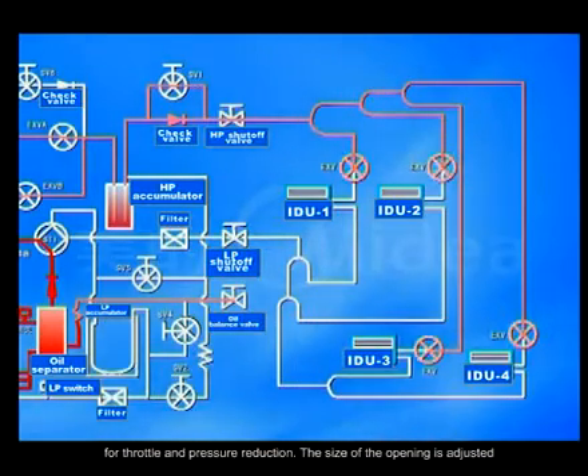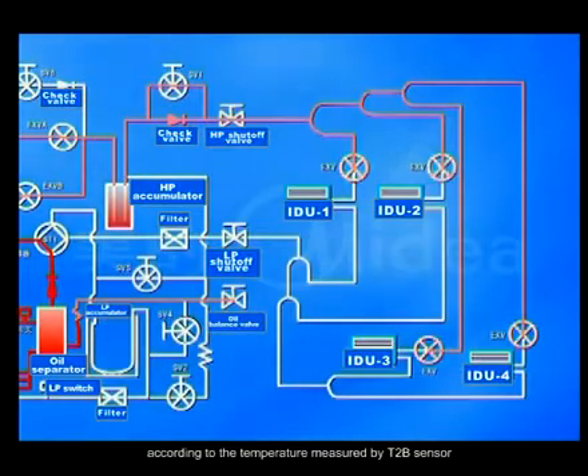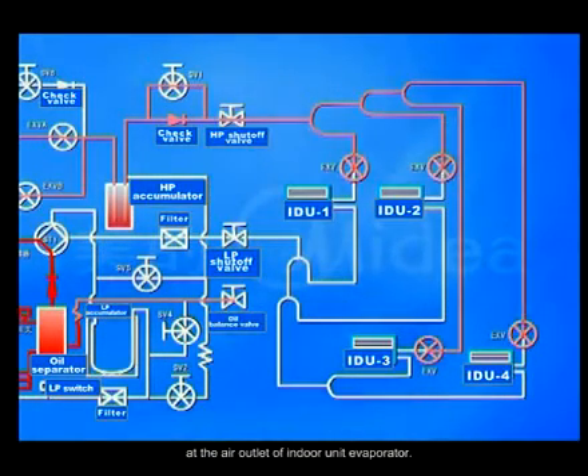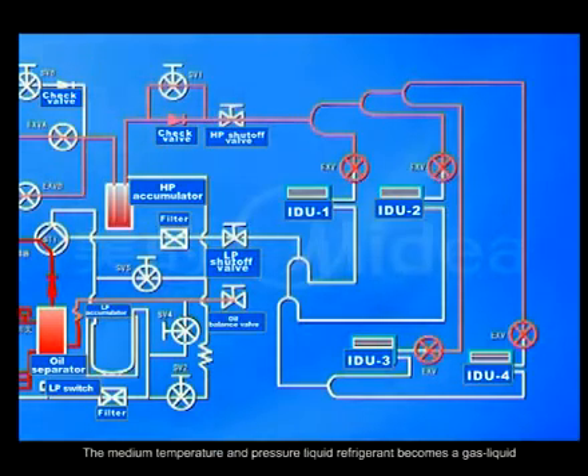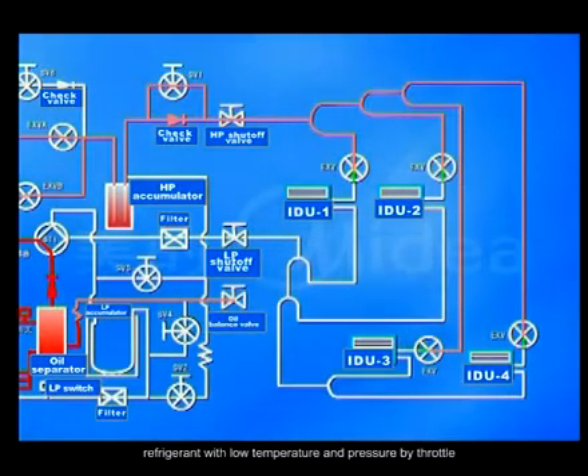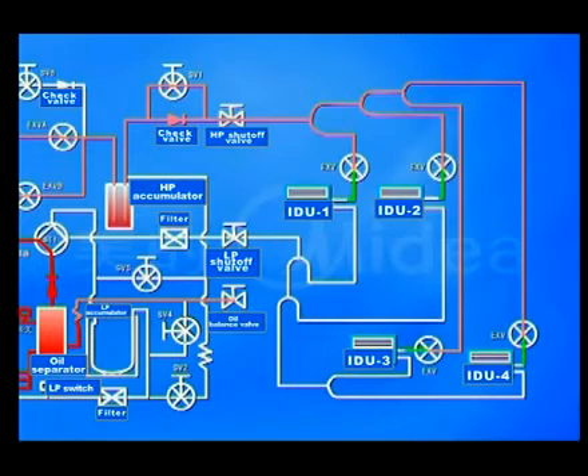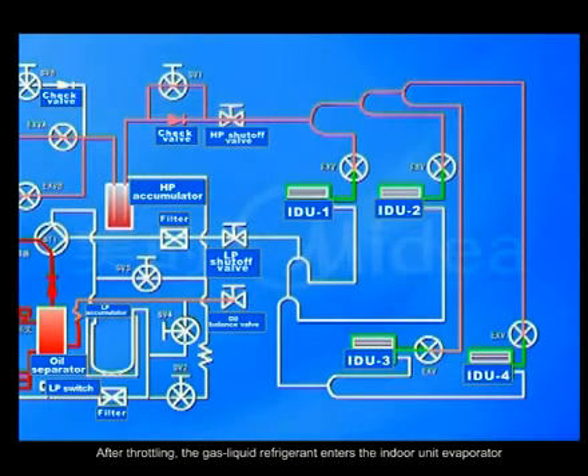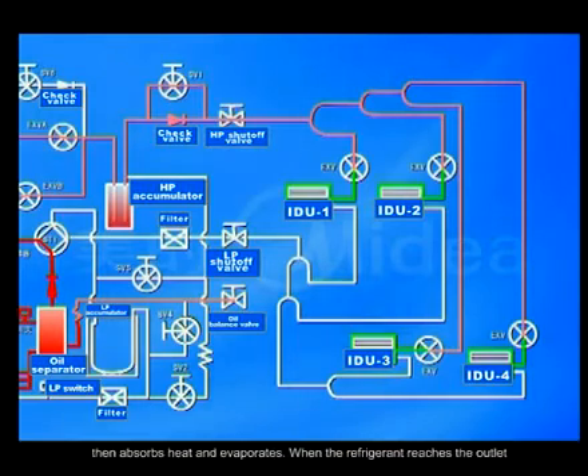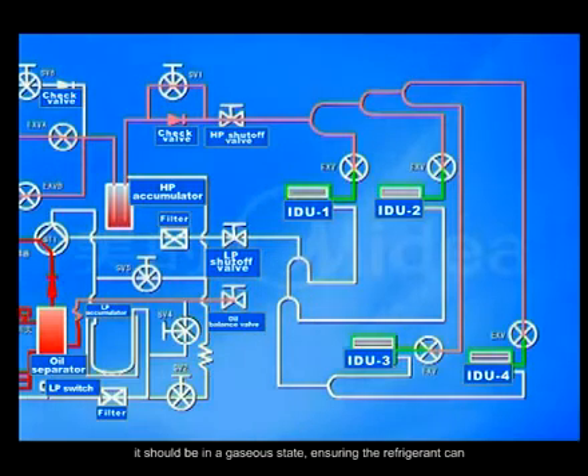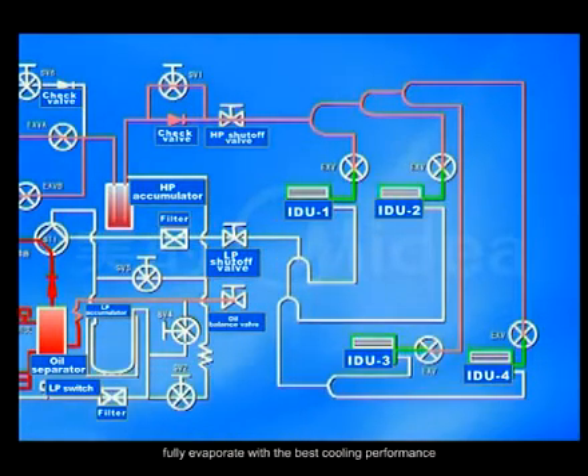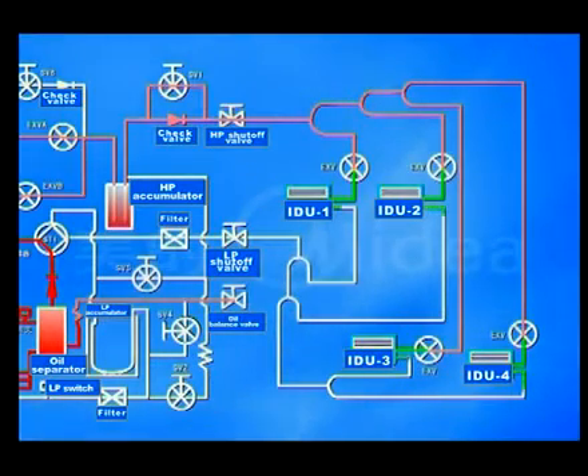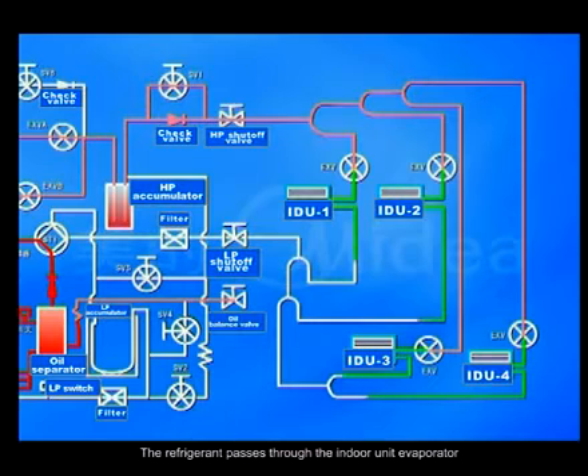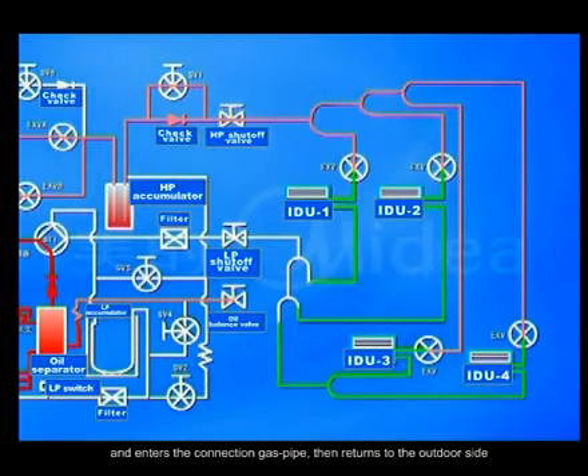The size of the opening is adjusted according to the temperature measured by T2B sensor at the air outlet of indoor unit evaporator. The medium temperature and pressure liquid refrigerant becomes a gas liquid refrigerant with low temperature and pressure by throttle. After throttling, the gas liquid refrigerant enters the indoor unit evaporator, then absorbs heat and evaporates. When the refrigerant reaches the outlet, it should be in a gaseous state, ensuring the refrigerant can fully evaporate with the best cooling performance. The refrigerant passes through the indoor unit evaporator and enters the connection gas pipe, then returns to the outdoor side.